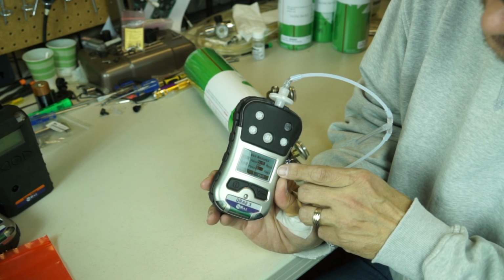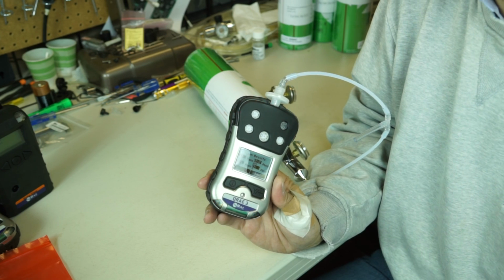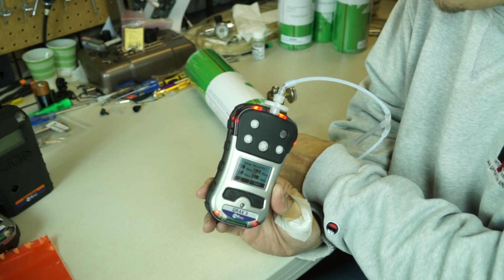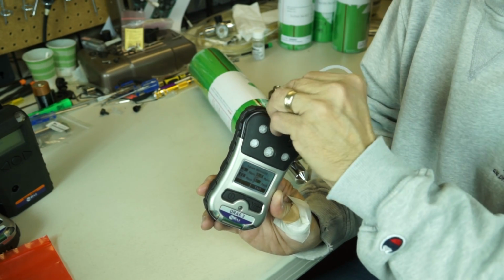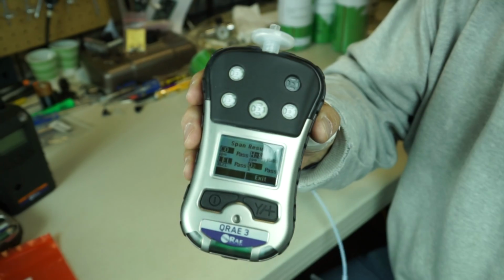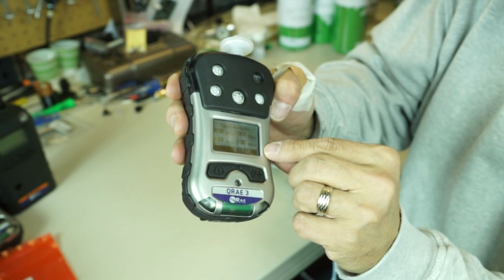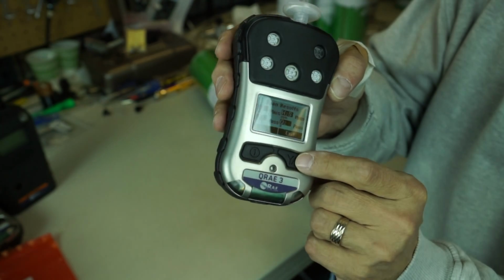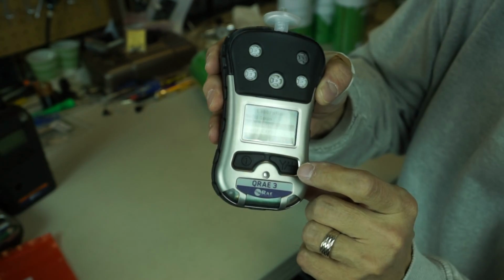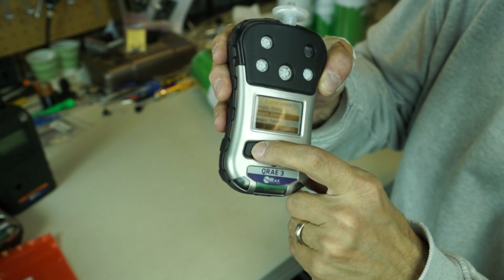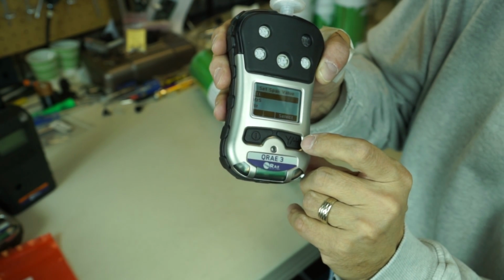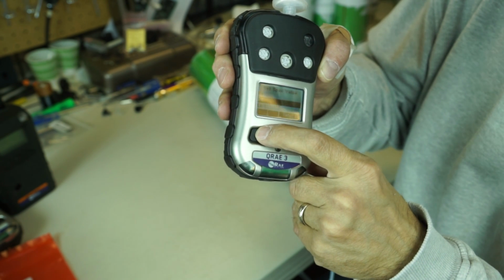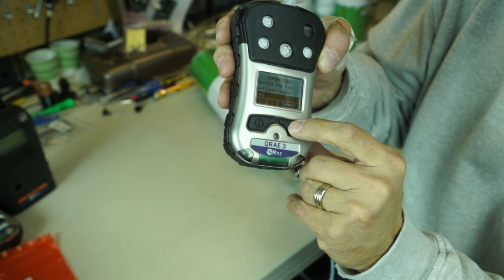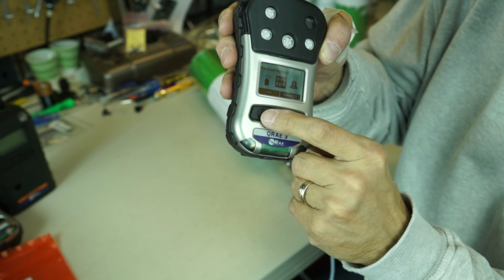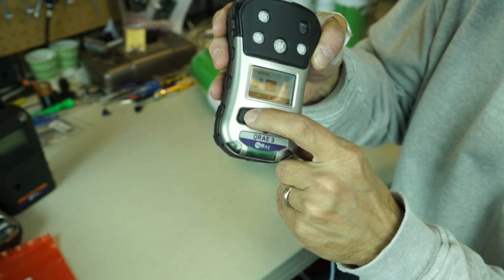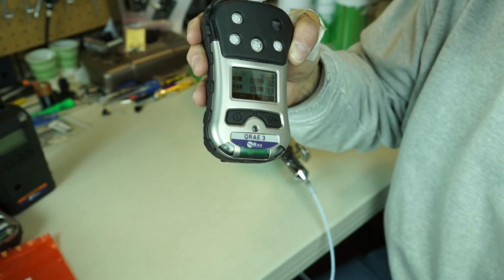It gives me all my readings of my instrument. It says pass, pass, pass, pass. Instrument goes into alarm. At that point, I can shut my gas off. I can disconnect my T. Show you that. And all I have to do is hit the exit choice, exit. Scroll down to where it says exit. Scroll over to the exit on the main menu. And I'm back in business.